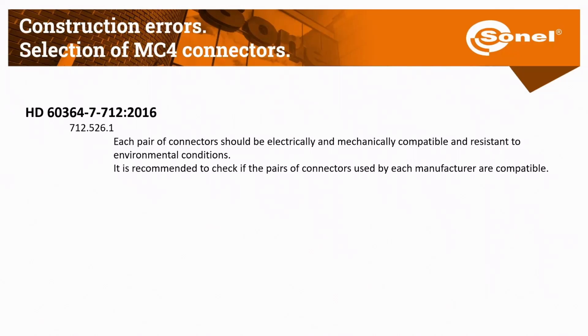Even it's described in the norm that each pair of the connectors should be electrically and mechanically compatible and resistant to the environmental conditions. It is recommended to check the pairs of the connectors used by each manufacturer as compatible. From the whole process, I would say this is one of the crucial things. The most common problems with the installation is a problem on the connectors or the continuity of the equipotential bonding.